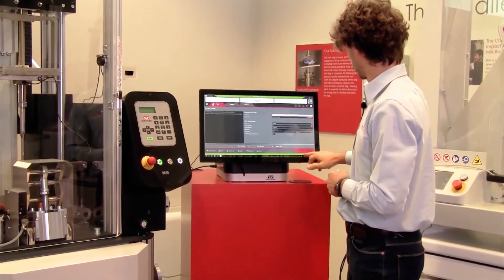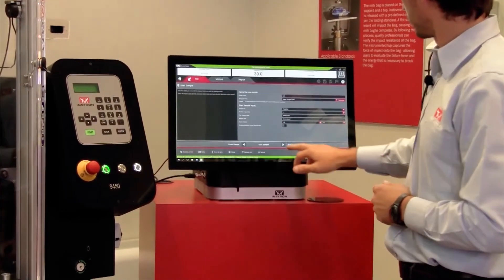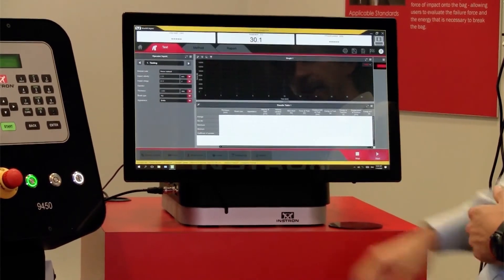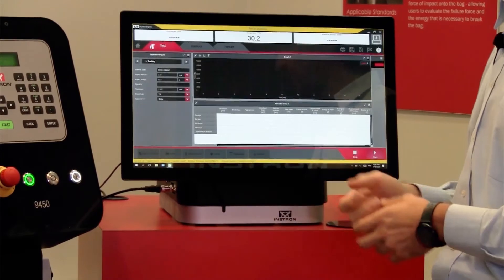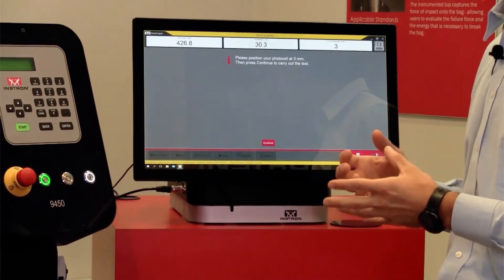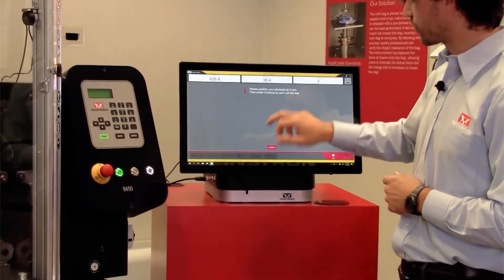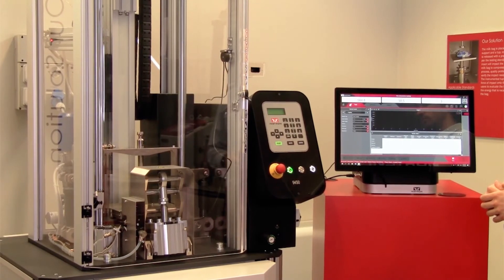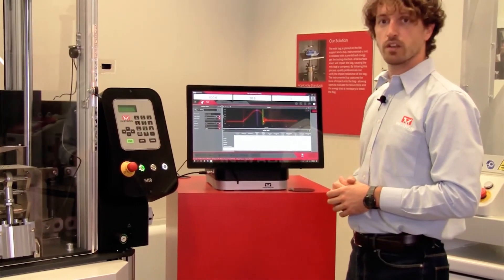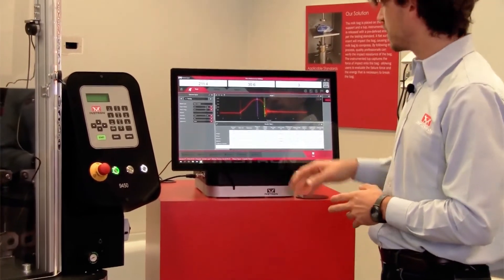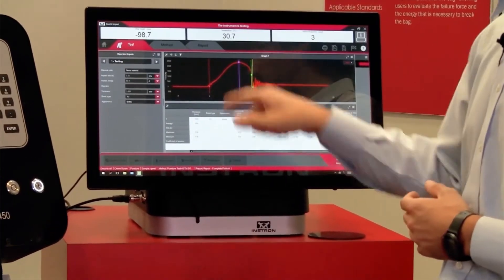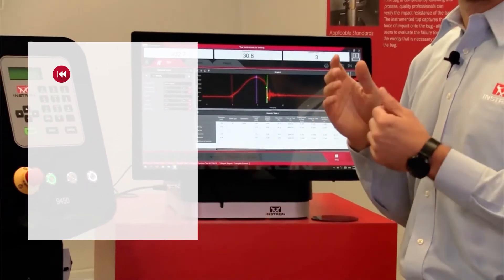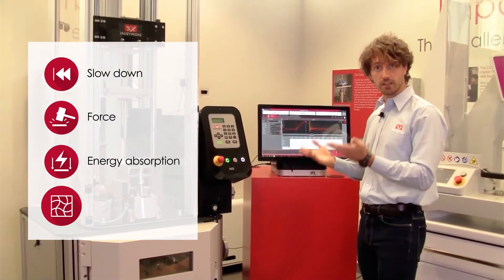Let's set a new sample name. We are finally ready to start a new test. As you can notice, the external frame changes color, providing a clear picture to the operator on the status of the machine. After confirming the photocell offset, the system starts moving. Just milliseconds after the test, it's possible to have the test results available, which include the graph, force-deformation or force curves, energy absorption, and deformation of the system.